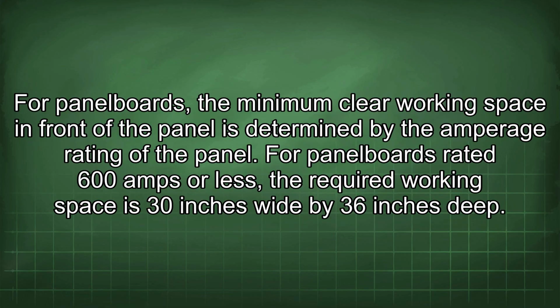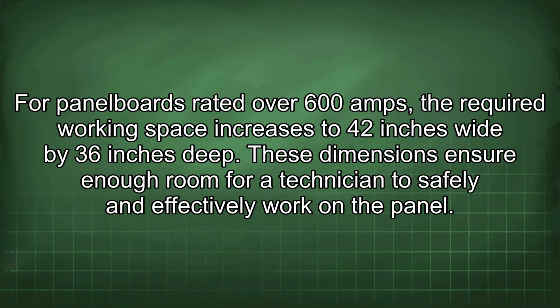For panel boards, the minimum clear working space in front of the panel is determined by the amperage rating of the panel. For panel boards rated 600 amps or less, the required working space is 30 inches wide by 36 inches deep. For panel boards rated over 600 amps, the required working space increases to 42 inches wide by 36 inches deep. These dimensions ensure enough room for a technician to safely and effectively work on the panel.